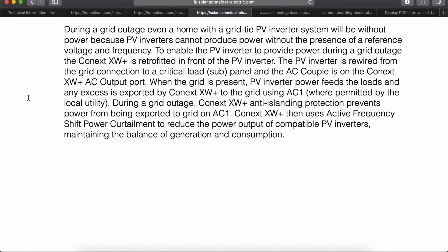To enable the PV inverter to provide power during a grid outage, the Conext XW Plus is retrofitted in front of the PV inverter, meaning in between the grid and the solar. The PV inverter is rewired from the grid to a critical load or sub-panel, as we say. The sub-panel and the AC couple is on the Conext XW Plus AC output port. When the grid is present, the PV inverter power feeds the loads, and any excess is exported by the Conext XW Plus to the grid using AC1, where permitted by the local utility, of course.